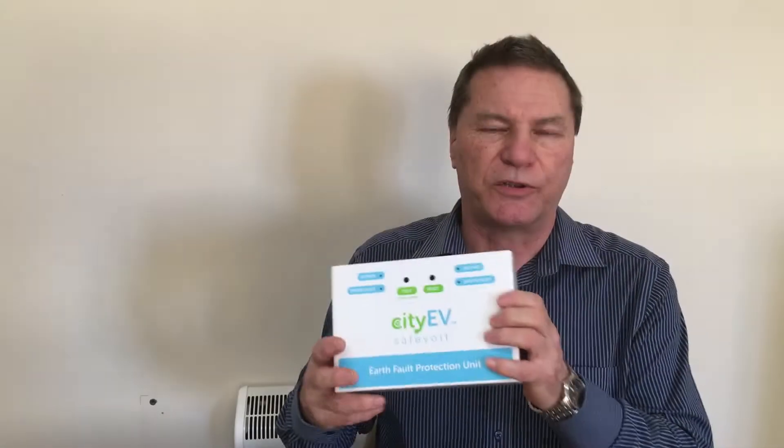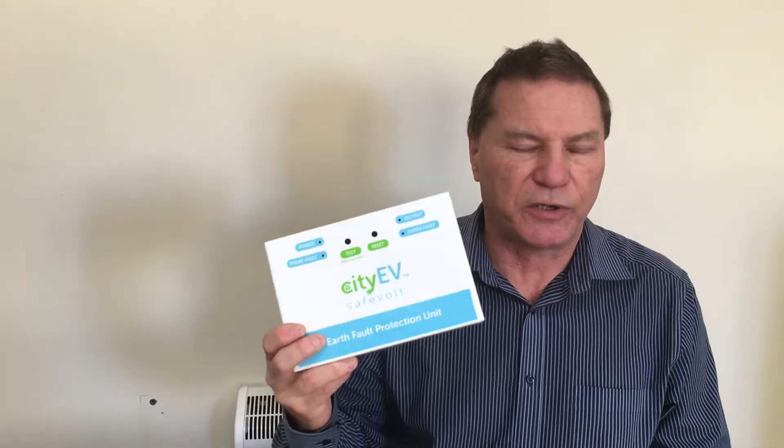The third option is to provide a device which can measure the voltage between true earth and the PME earth within a building. If this voltage rises above the prescribed safety limit of 70 volts, then the device must disconnect the live and protective conductors from the charge point. The cityEV safeVolt is such a device.